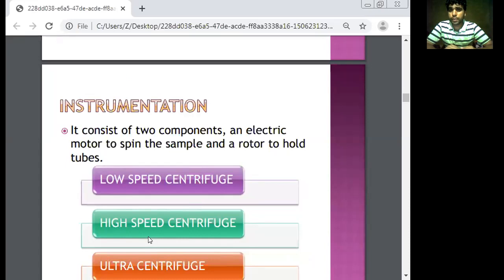The instrument consists of two components: the electrical motor to spin the sample and the rotor to hold the tubes.